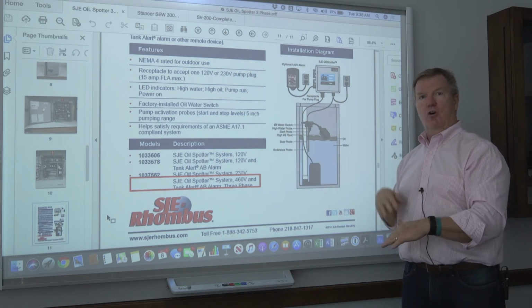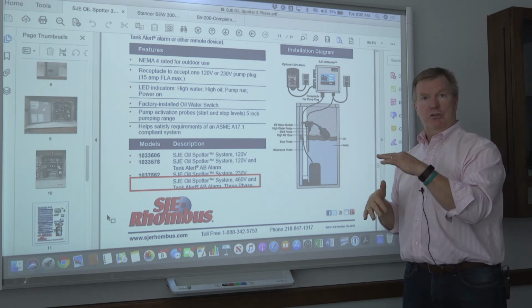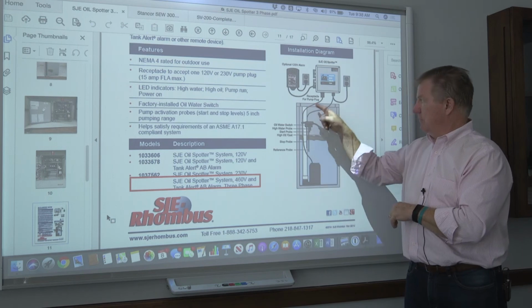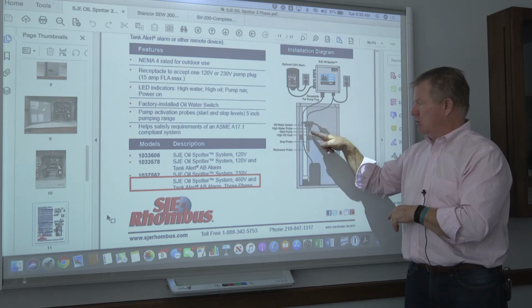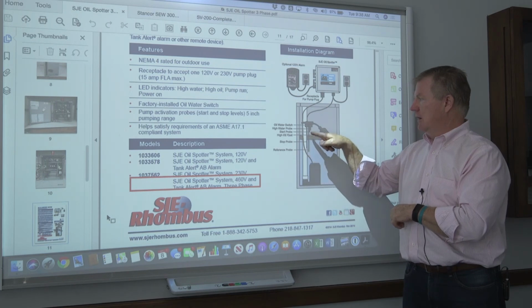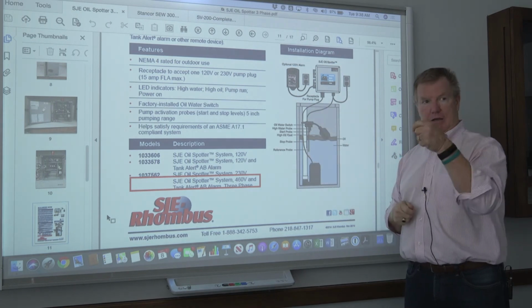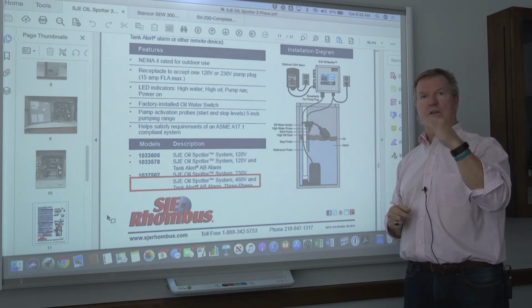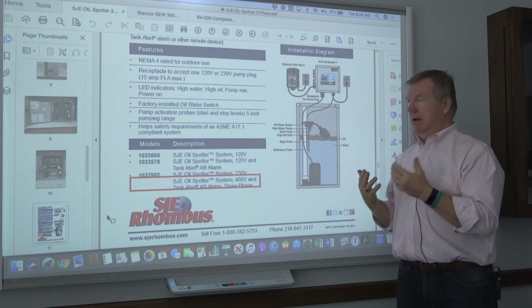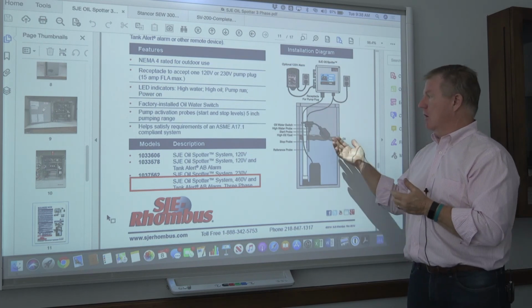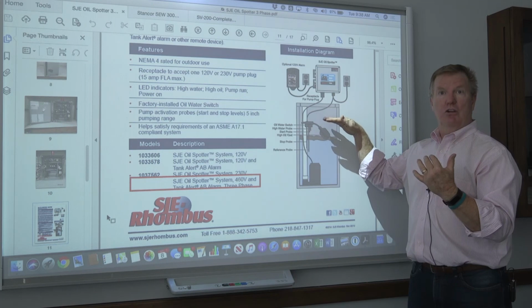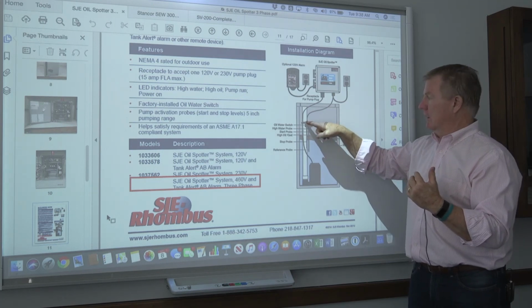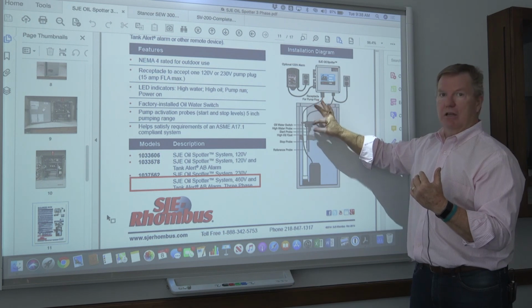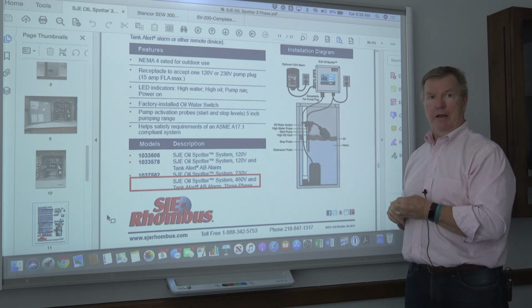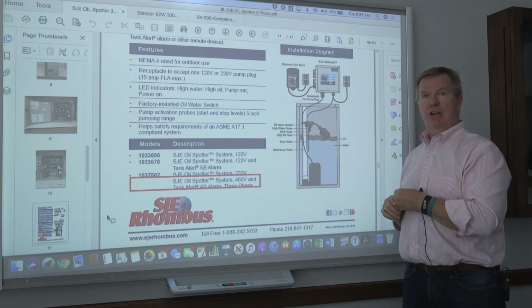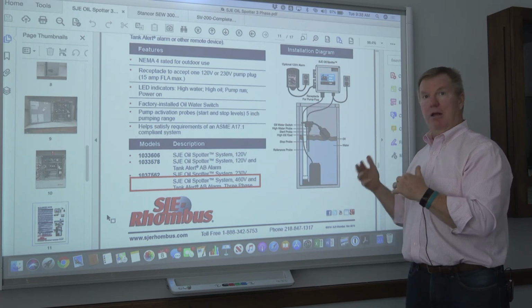the sump pump turns on and off at, you can either dump some water in there and watch it and take measurements, or you can measure from the top down or from the floor up to the bottom of each one of these probes, the stop probe, the start probe, and the high water probe, and you can give a report that says here's what levels those normally operate at, so that you know that it's working. And if you don't like the levels and you want it to turn on a little bit lower, you can adjust the height of this entire assembly up and down on that pipe or whatever it's attached to, to change the start and the stop and all the alarm levels.